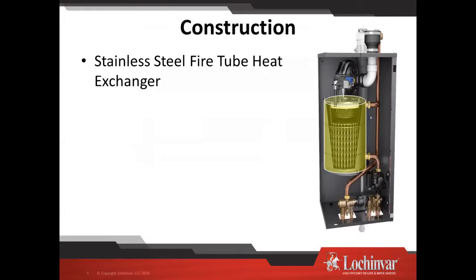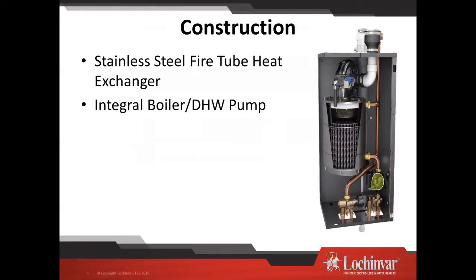We're going to talk about the heat exchanger. It is a fire tube design, so it does clean a little differently than a water tube. The boiler pump is built into it. The boiler domestic hot water pump is built in to the combi unit. If you have a boiler only model, it does not have a pump built into it. The pump is going to be external. So we're going to look at.